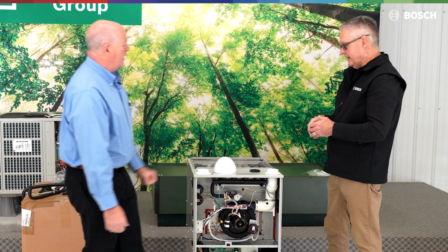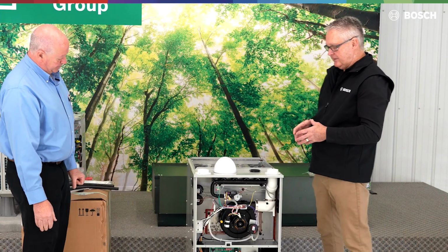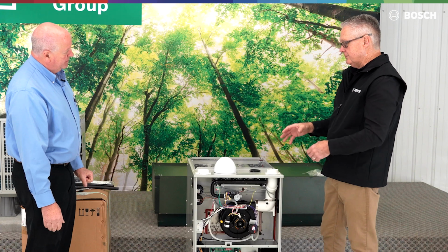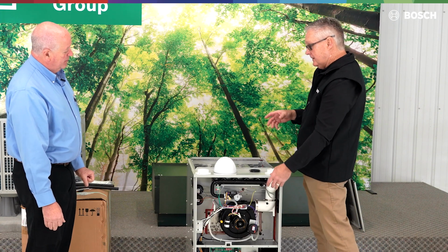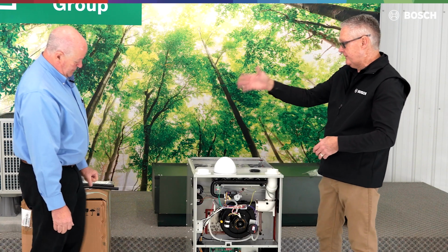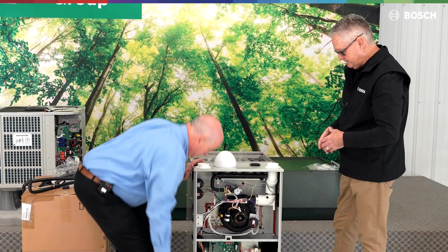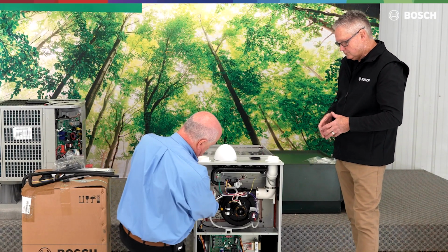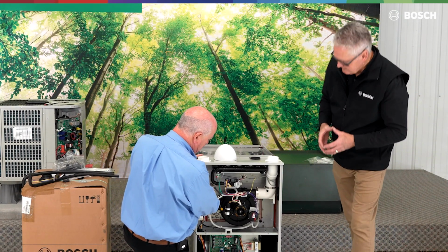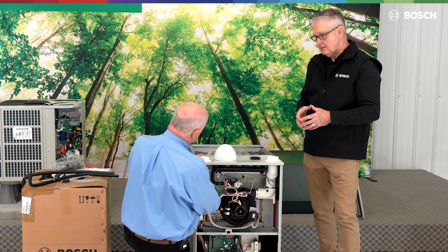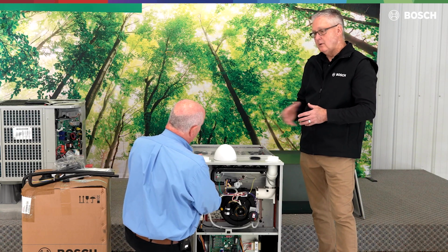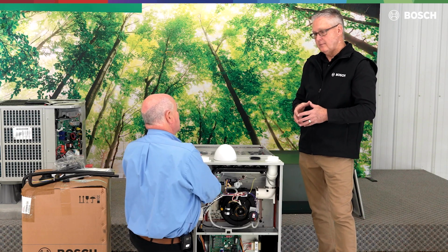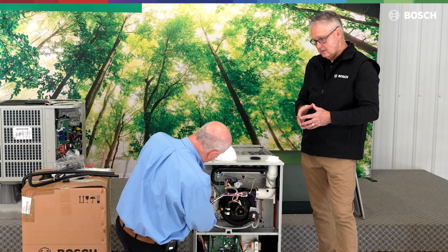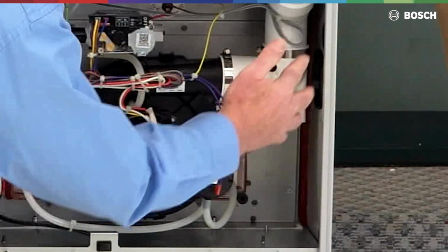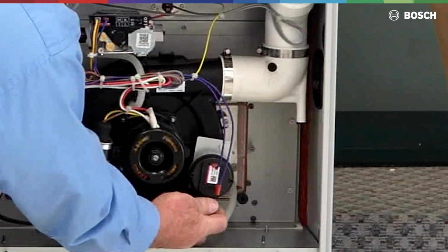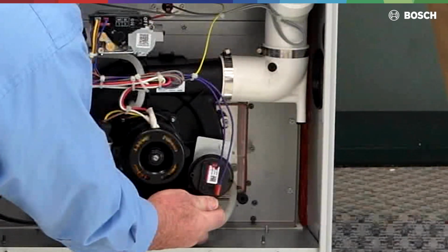Yep, we're going to cover that in more detail. It's all in the IOM, and there are some things that we've got to make sure that we manipulate and change because of the configuration that we're going to be going into. Some of those things are the pressure switches. And as long as we're on this right-hand return, left-hand blow, right-hand blow, left-hand return, I don't need to move the pressure switch. Exactly. But if I turn that around, these switches are on the bottom, they have to be moved to the top. And I believe there are some configurations where we swap these 2 hoses out on that one pressure switch as well. Yep.